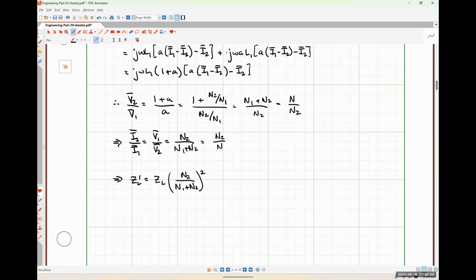That's isolation transformers. You'll see that in a lot of electronic equipment. For auto transformers, there is no isolation between the two coils because there isn't two coils, there's just one coil that's split up. So you'll see auto transformers used a whole lot in substations because you want the smallest possible footprint for all of that large equipment.